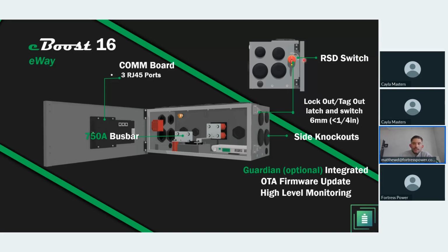Both this switch and the latches of the door of the E-way are lockout and tag out friendly, as long as you use a lock that's 6 millimeters, which is the exact measurement. It has side knockouts, and it includes a DIN rail to include the Guardian, which is Fortress Power's monitoring hub, in order for you to see all the intricate details of the battery, state of charge, voltage, current, not just on a single battery, but all batteries paralleled together. You would only need one per system.